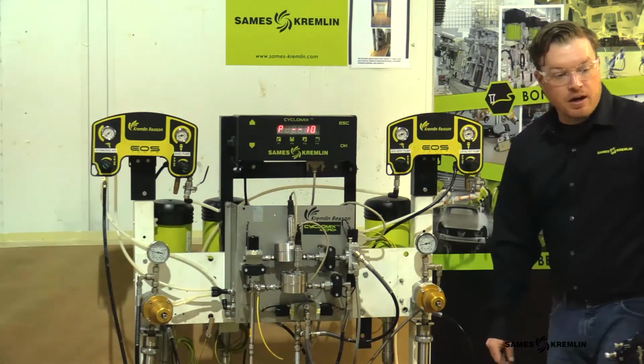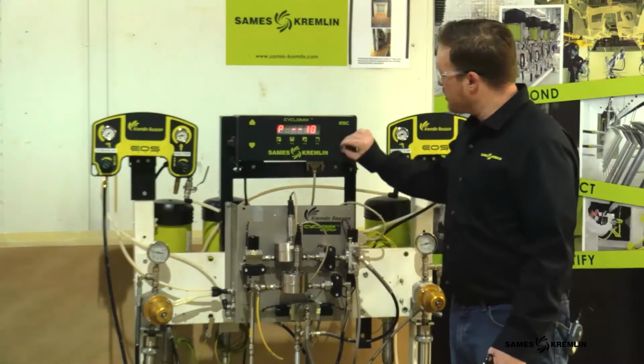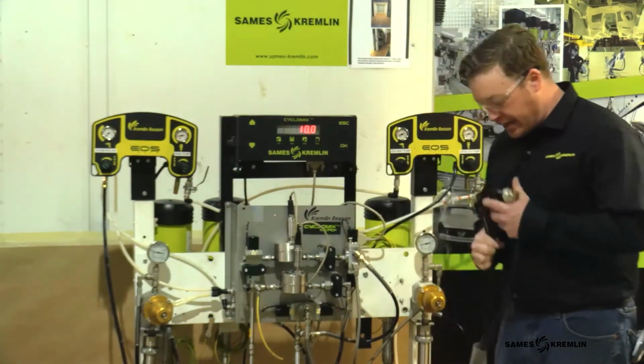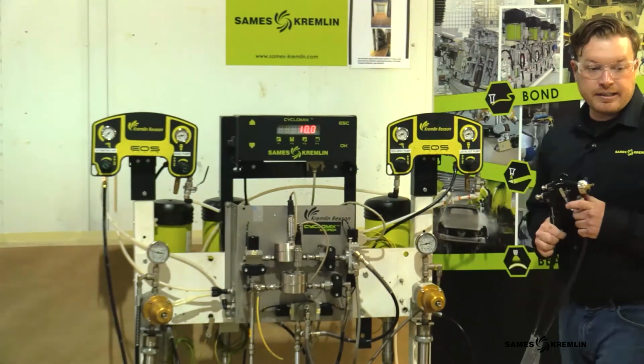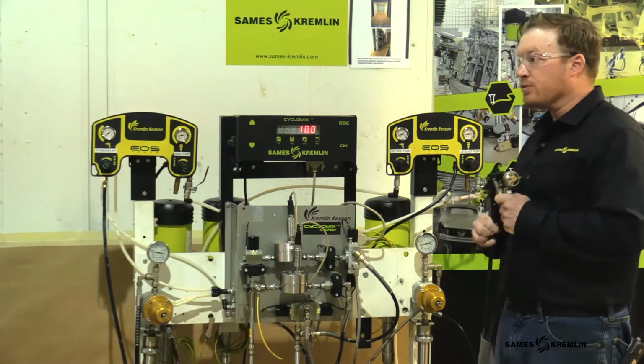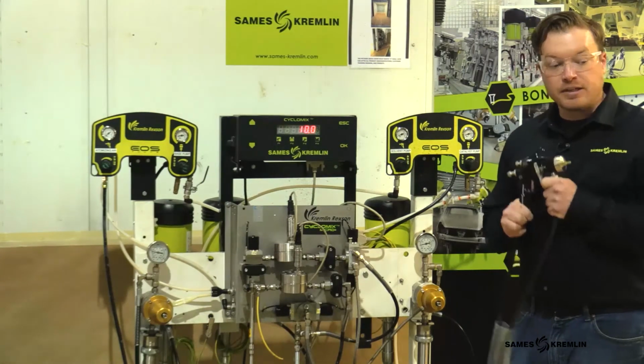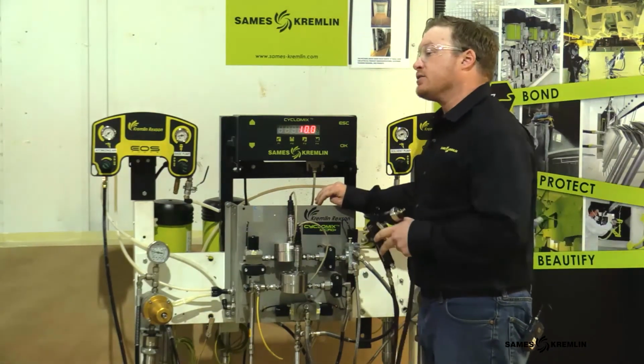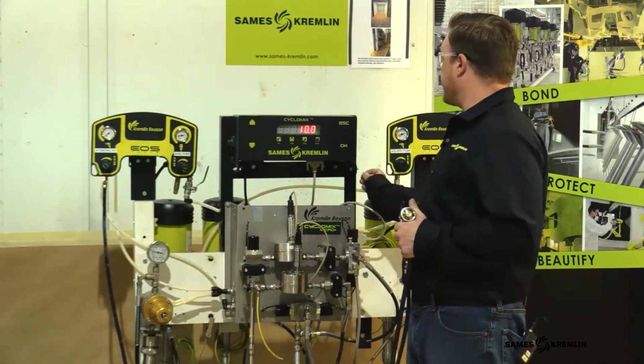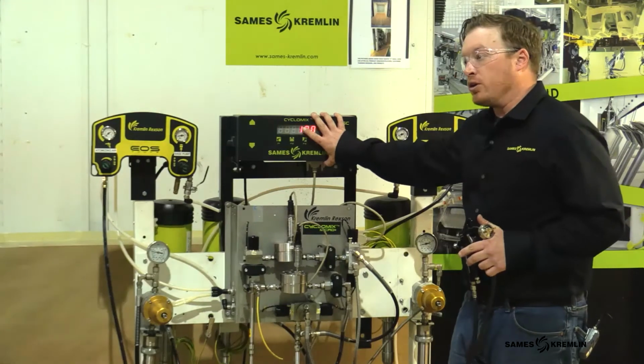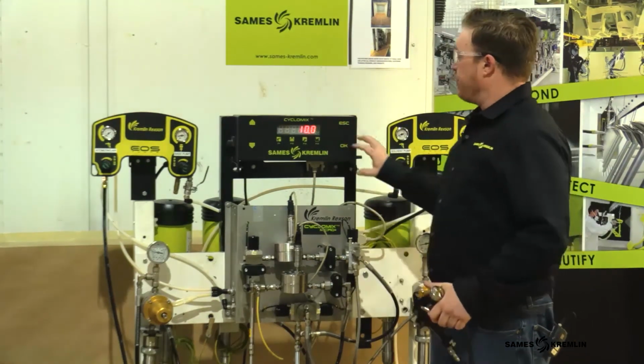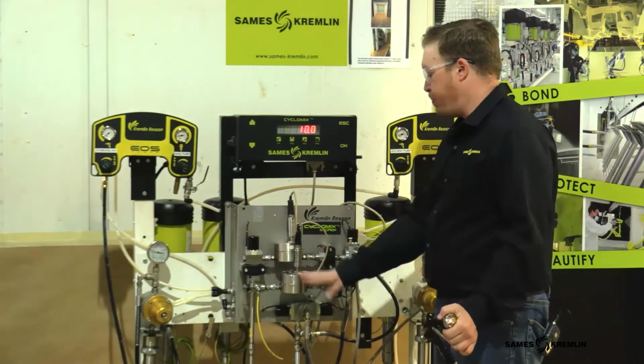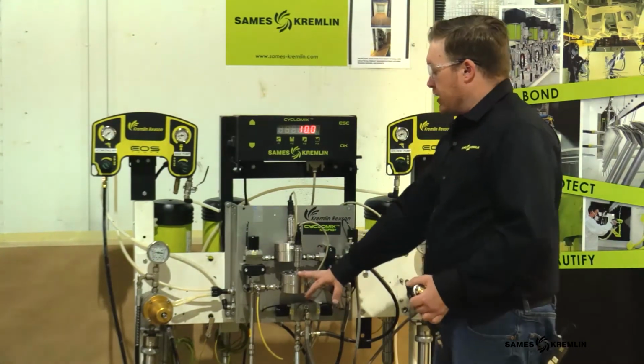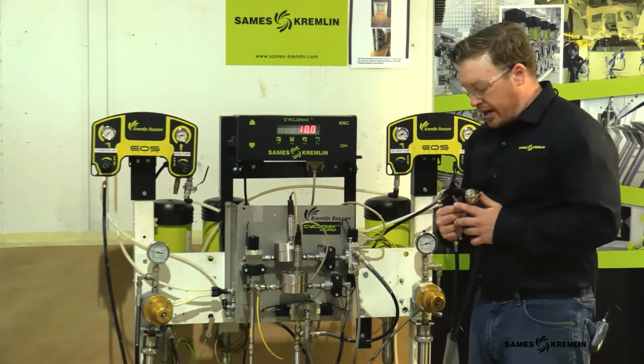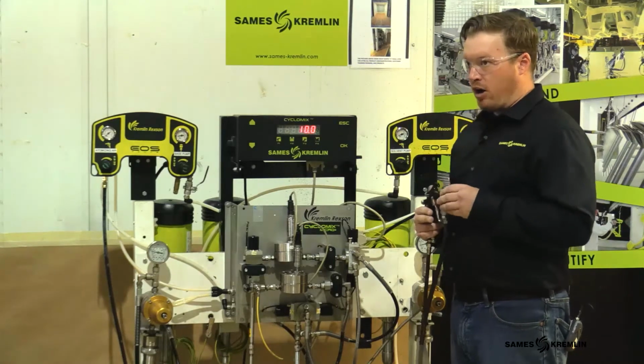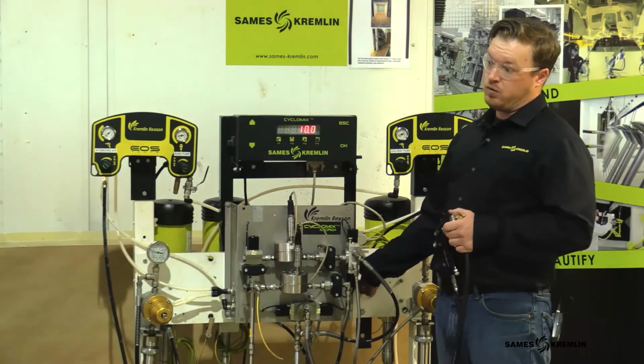Parameter 10 is going to be the amount of time that we have before the machine needs to see pulses from the flow meter. So the way that these machines work is that there are 2 signals required for the controller to be happy. One of those signals is pulses from the A flow meter, and the other signal is a 24 volt on off coming from a flow switch in the back of the mix manifold.